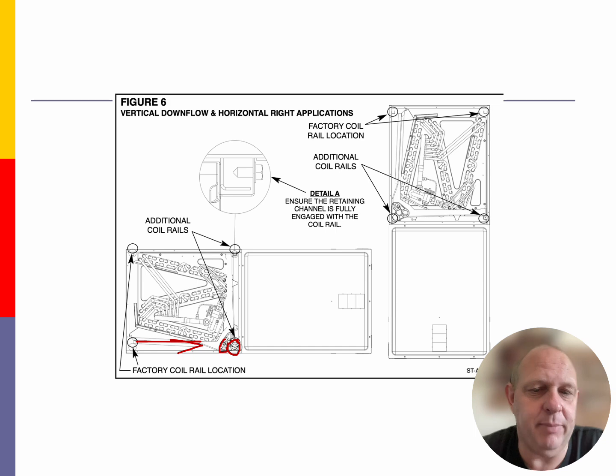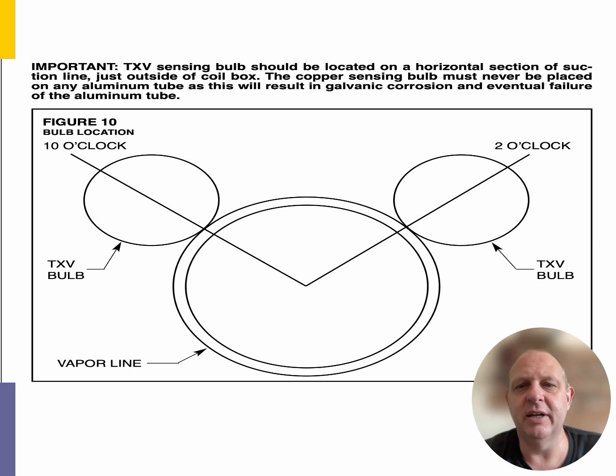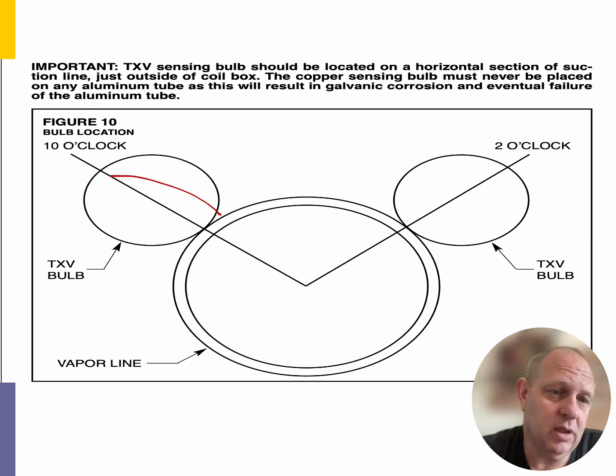The last thing that we're going to be discussing will be the location of the TXV bulb, if you happen to have a TXV. For this manufacturer, and like I said, go back to your manufacturers and read the manuals, and they'll tell you better where to put these. But we're looking at a 10 o'clock or a 2 o'clock area on top of the suction line. So this is the vapor suction line, and we want to install that particular sensing bulb on that suction line at a 10 or a 2 according to the manufacturer. This is going to sense how much liquid refrigerant we have in the system, and it's going to let that TXV adjust to the superheat values that are on it.